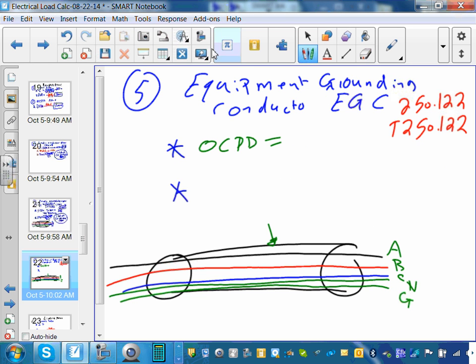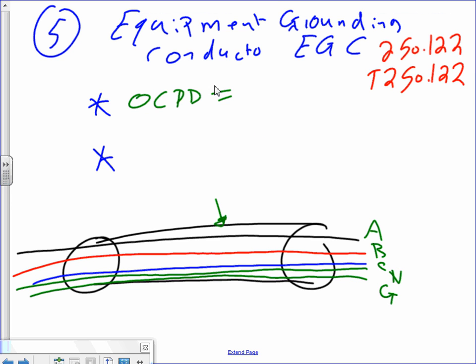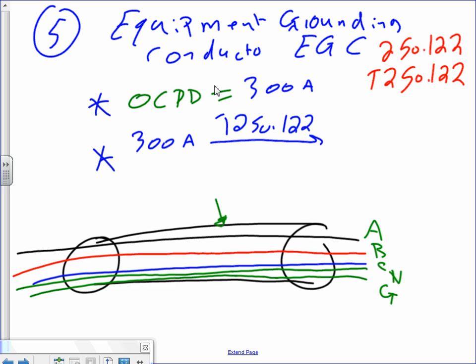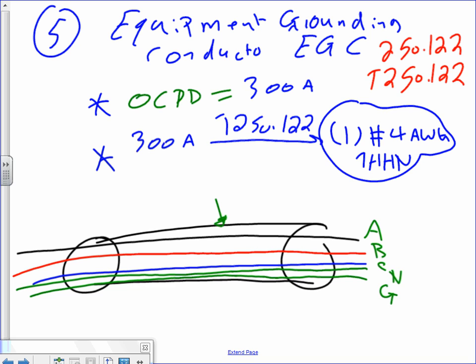No gimmicks, nothing. So we can go right here, gentlemen, to equipment grounding conductor. Okay, equipment ground conductor. We have 300 amp, right? You take your 300 amps and make sure you take it to table 250.122. When you go there, it will tell you one conductor, number 4 AWG, and typically THHN. Now, it could be bare, but typically when we put them in a conduit, guys, it's insulated like the others, with the green insulation on it.